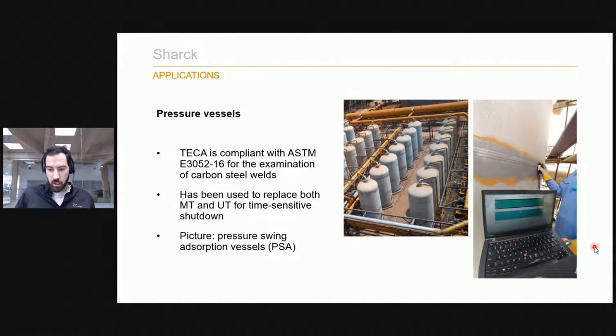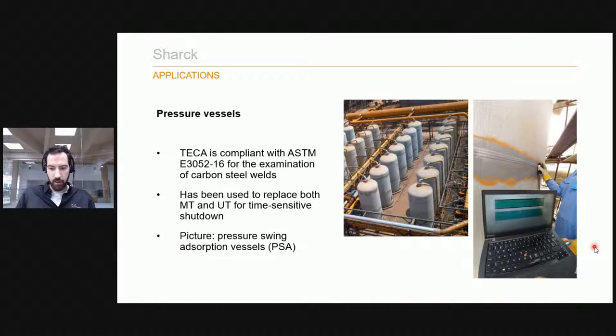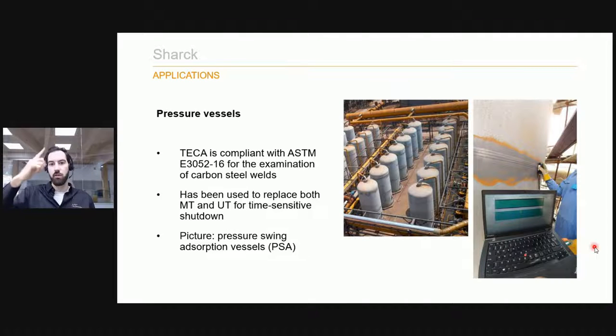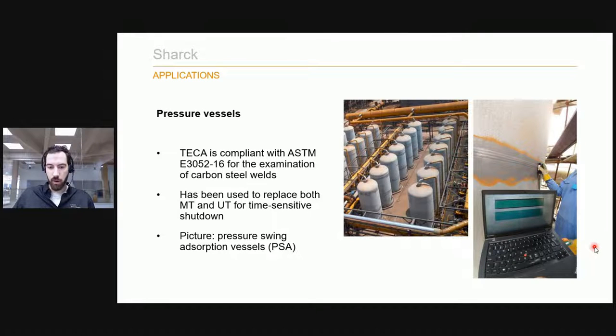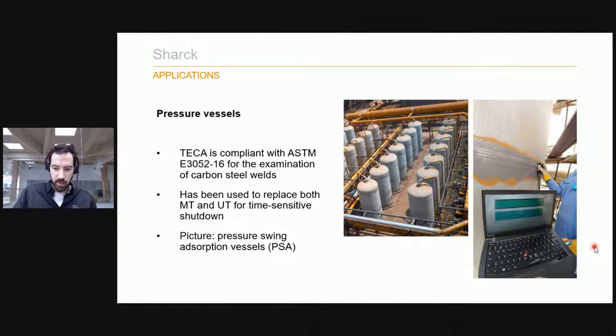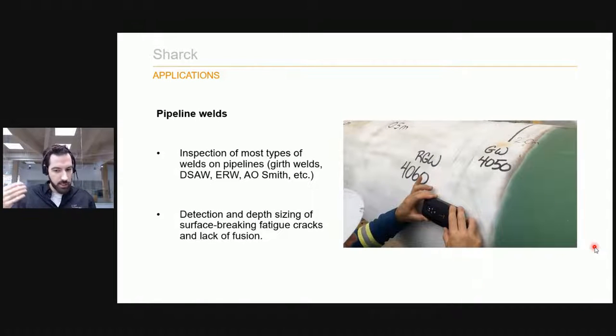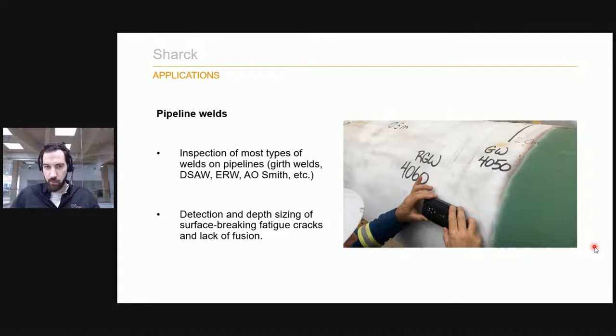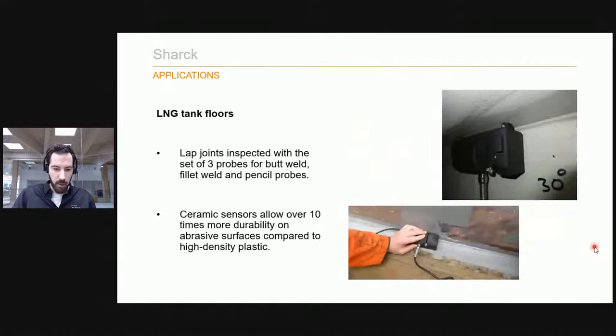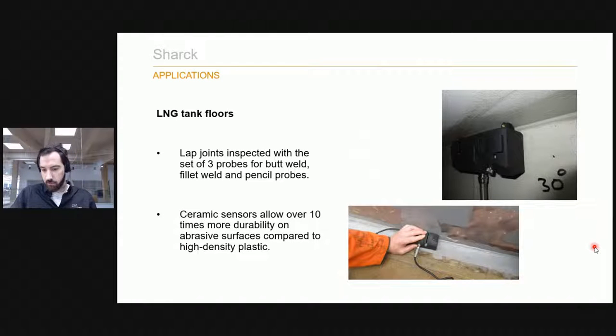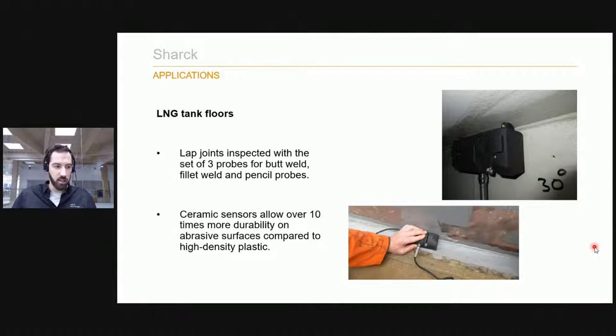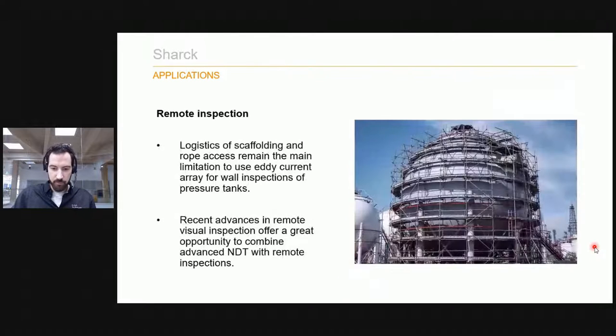Talking about applications, those probes have been used for pressure vessels in a lot of situations. You can do a 360 degree wraparound around your tank, your vessel, and inspect the full weld. That's of course much, much faster than visual inspection. Same with pipelines. Here we have a girth weld. You can wrap around the pipe with one scan, scan everything. The tank floors, you have those corner welds at the bottom. You just take the fillet weld probe, scan the entire weld. We're talking one, two minutes of scan, another one, two minutes of analysis. And that's it.